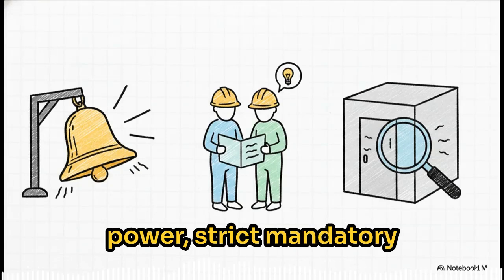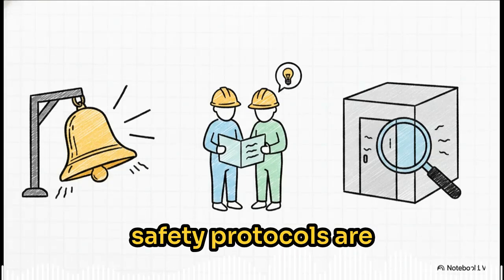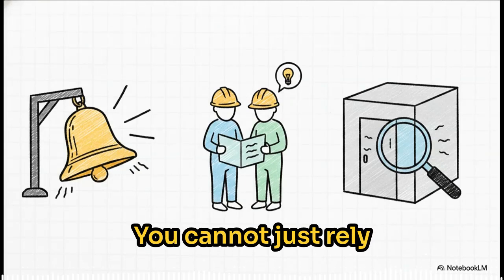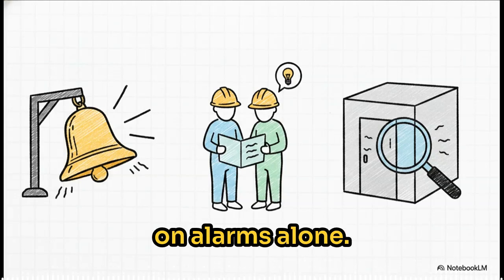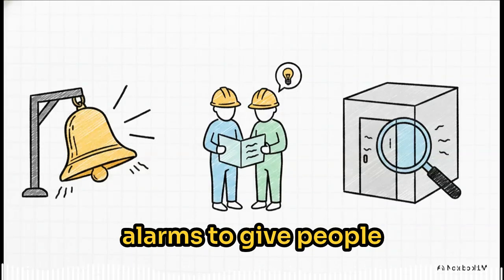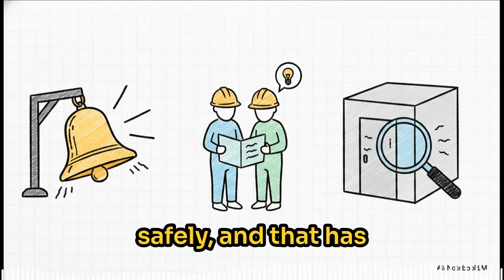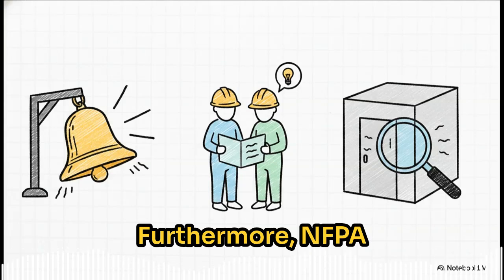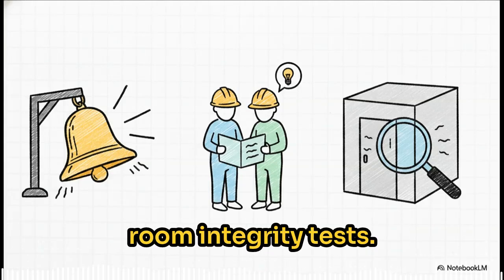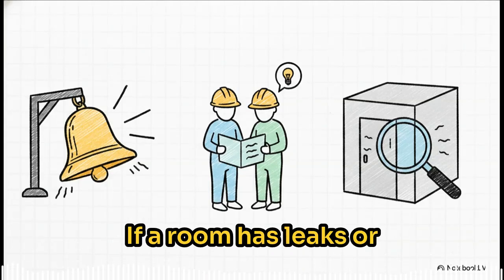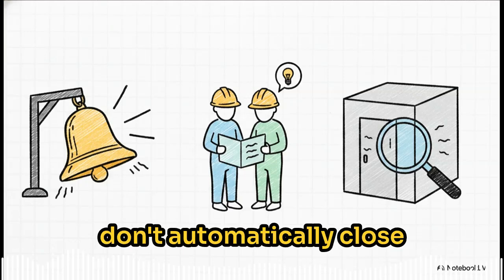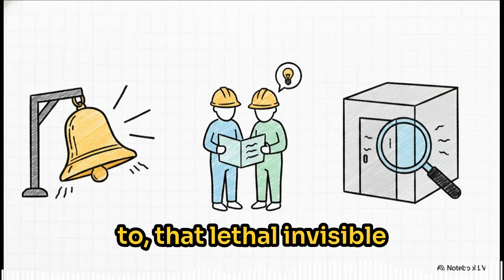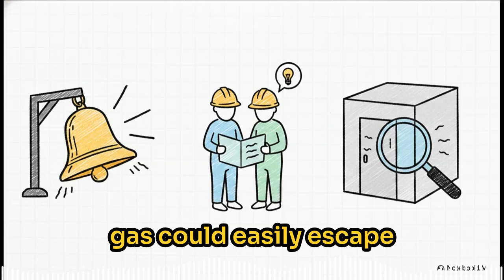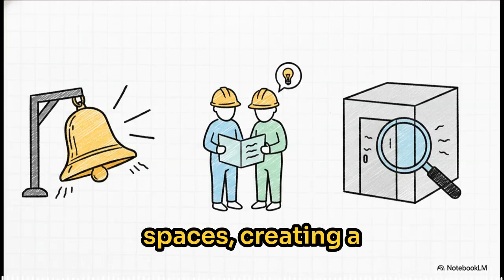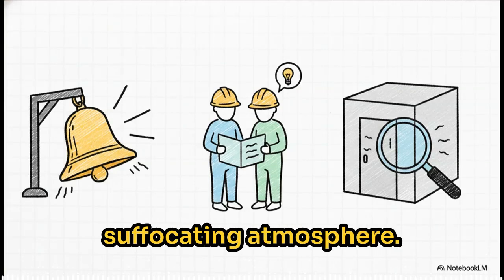Because of that lethal power, strict, mandatory safety protocols are an absolute necessity. You cannot just rely on alarms alone. You need pre-discharge alarms to give people time to evacuate safely, paired with comprehensive, rigorous personnel training. Furthermore, NFPA standards require annual room integrity tests. If a room has leaks, or if the HVAC dampers don't automatically close like they're supposed to, that lethal, invisible gas could easily escape into adjacent, occupied spaces, creating a completely undetectable, suffocating atmosphere.